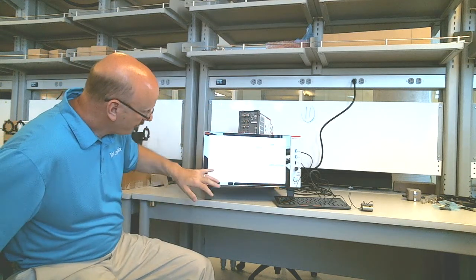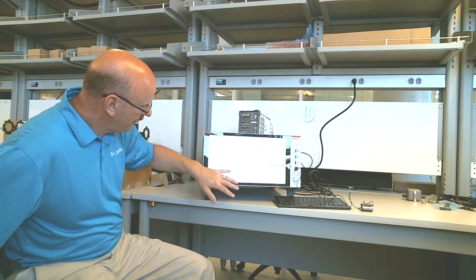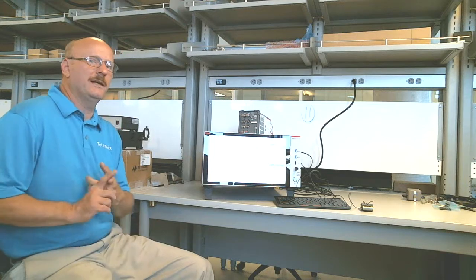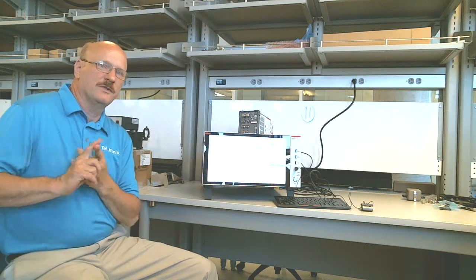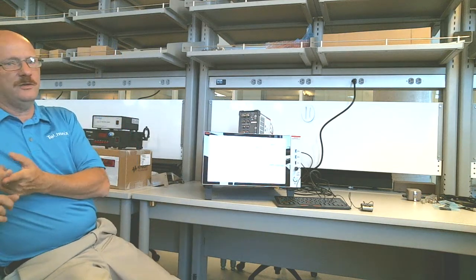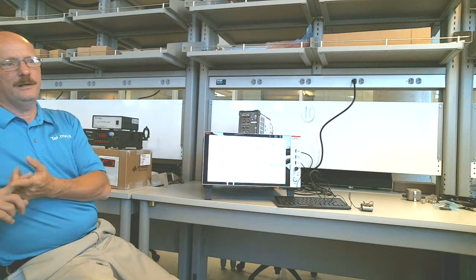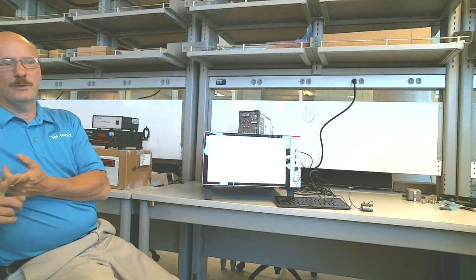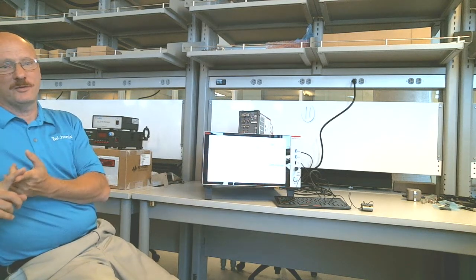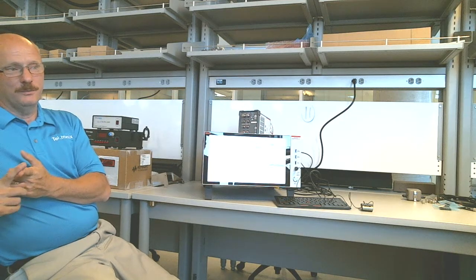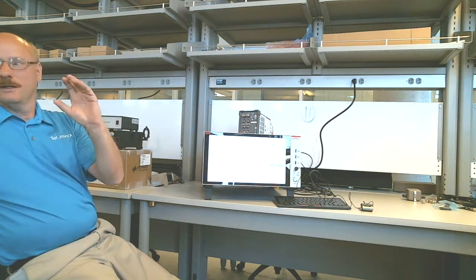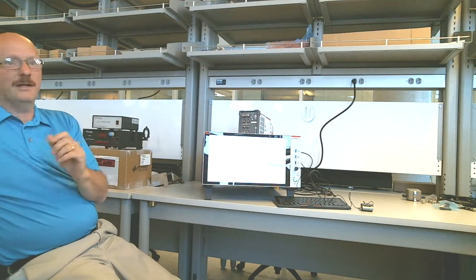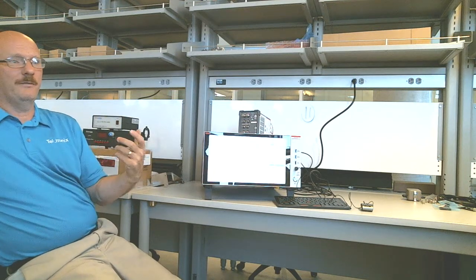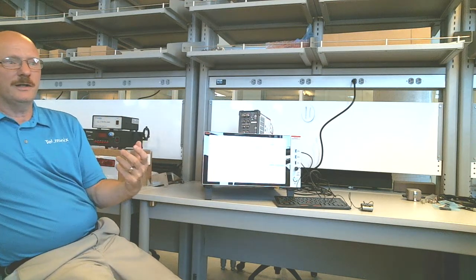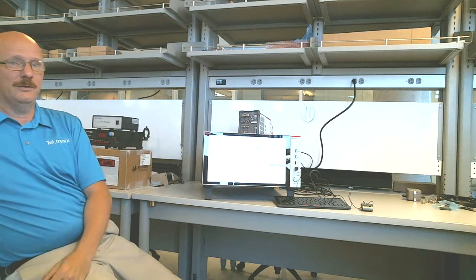Measure current, measure voltage - you have two A to D converters on every channel. So I can source a voltage and measure a current and a voltage. I can read back the voltage I'm sourcing, which is very cool, because if you have any loading on your source you'll see that. Otherwise you're using the program value, which is not going to be as accurate as the read back value, right?